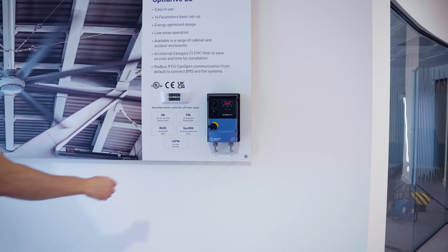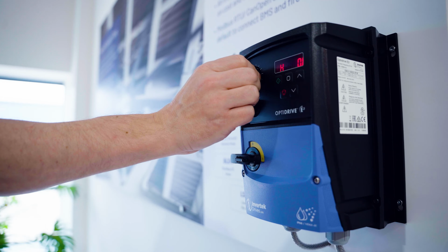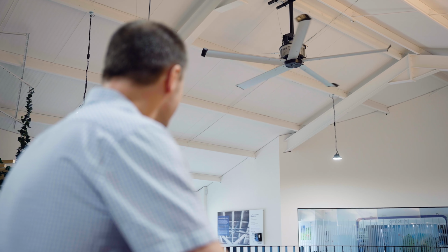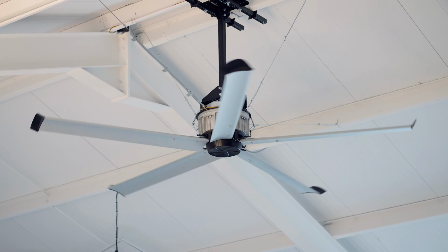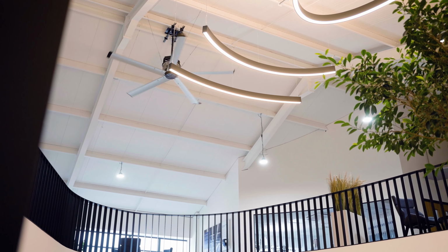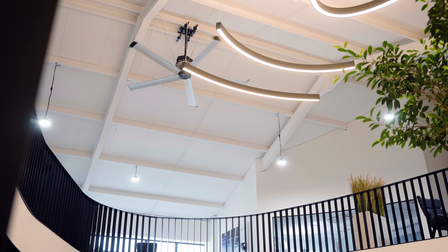In the atrium outside here we have a large diameter destratification fan. This is an application that has really grown over the last few years for us. Large diameter fans operating at relatively low speed, and the idea of those is that they circulate air round within a building. So where you have an area like our atrium with a very high ceiling height, of course hot air rises to the top, and these destratification fans can be used to push that warm air back down so that we regulate the temperature throughout the building.